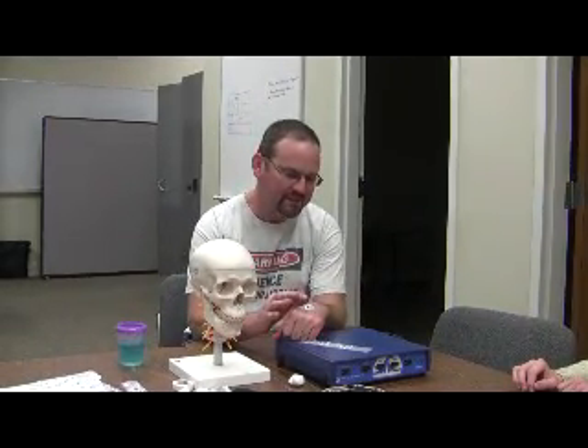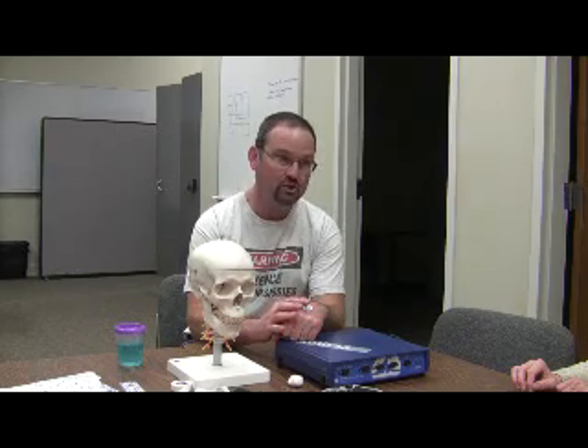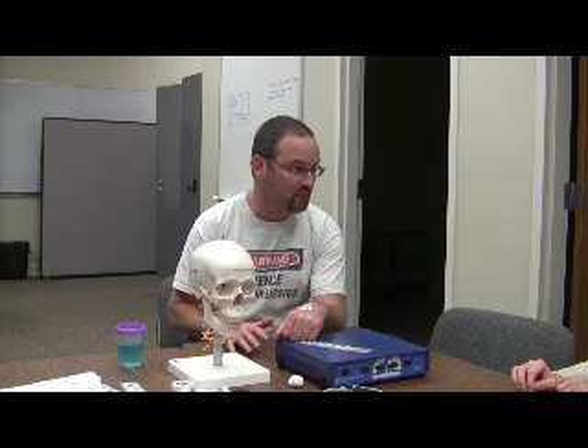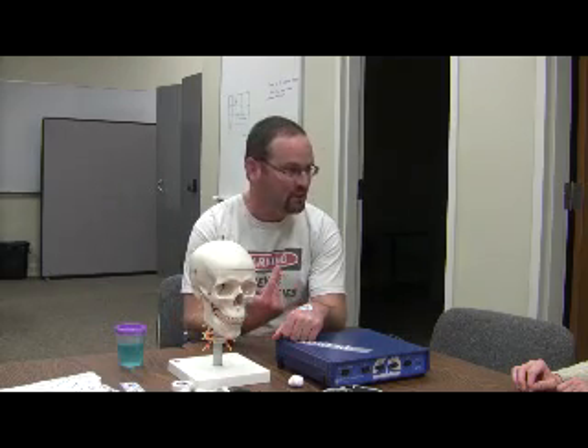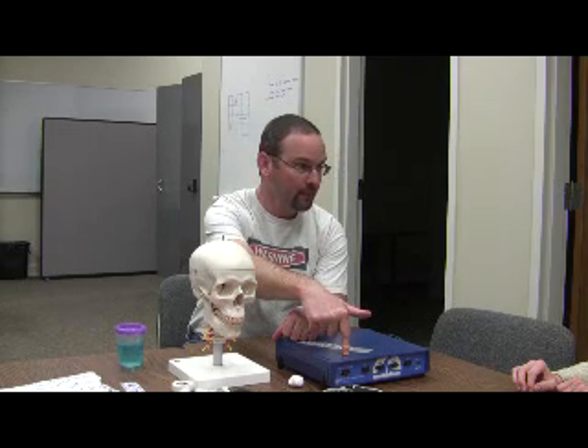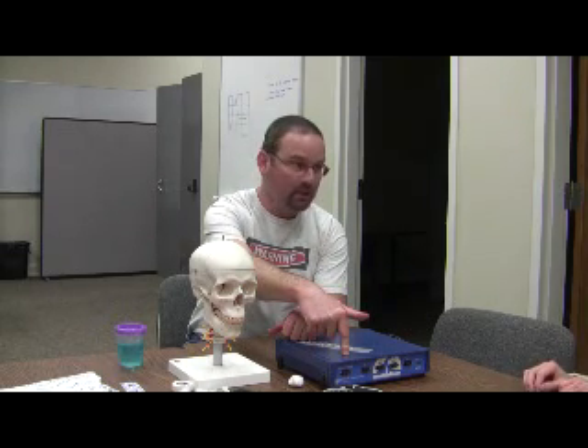Think of it like saltwater jello — although it's not gelatin like you'd eat. It is non-toxic. Most importantly, it's a semi-liquid state electrical bridge. We're interested in electrons that play across the surface of your skin and getting them into a wire, which will go into the amplifier. We're interested in creating currents.